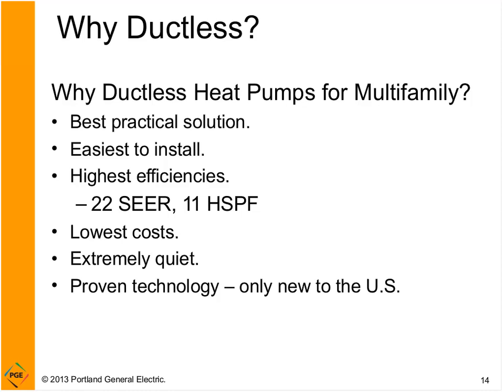Highest efficiencies. So SEER is a seasonal energy efficiency ratio, and it's kind of a standard for an efficiency rating over the season for cooling. So for ductless, we see units with up to 22 SEER. And to put things in perspective, the current minimum standard for heat pumps and air conditioners is 13 SEER.